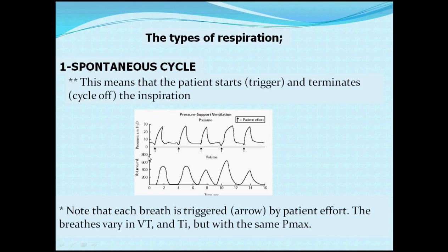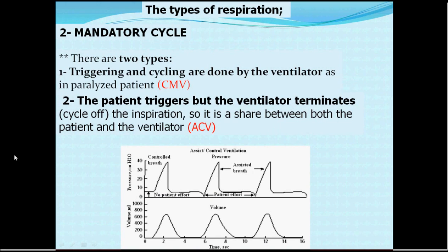Finally, types of respirations are divided into spontaneous and mandatory. In spontaneous breathing, the patient triggers and terminates the cycle — both initiation and termination are by the patient. In mandatory ventilation there are two subtypes: controlled mandatory ventilation, where triggering and cycling are both done by the ventilator (as in paralyzed patients); and assisted mandatory ventilation, where the patient triggers but the ventilator completes and terminates the cycle — as in assisted control volume-controlled ventilation.